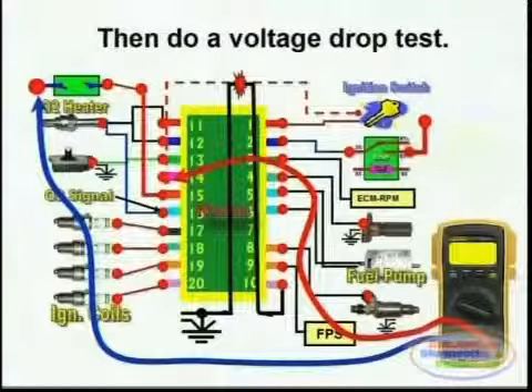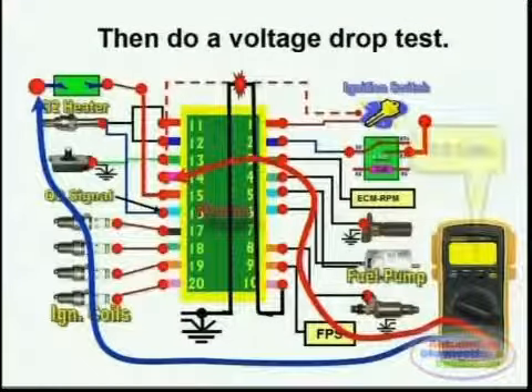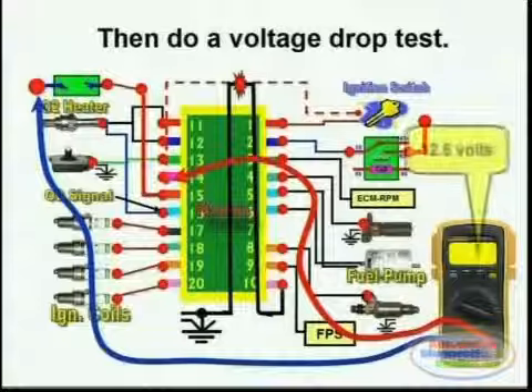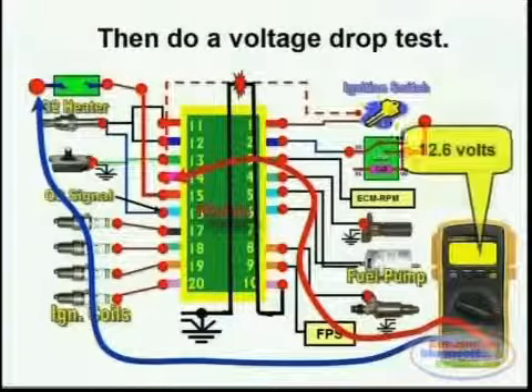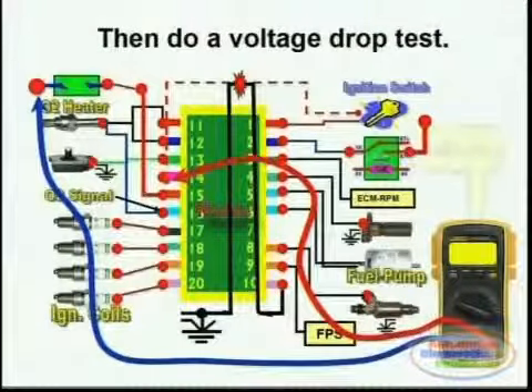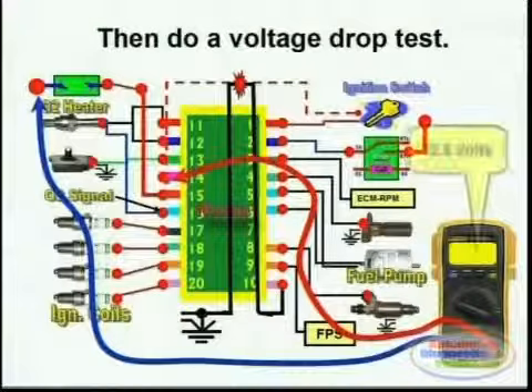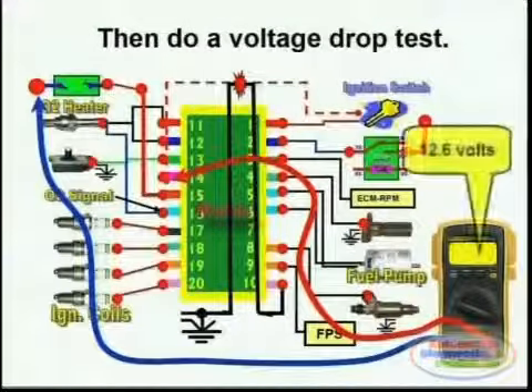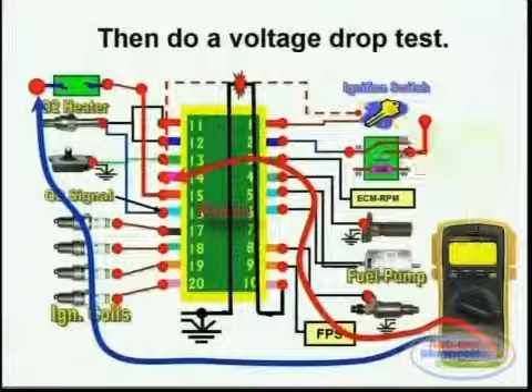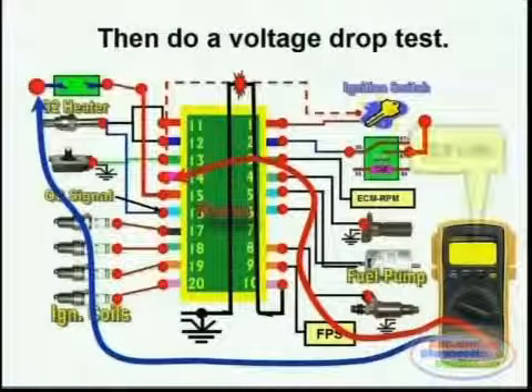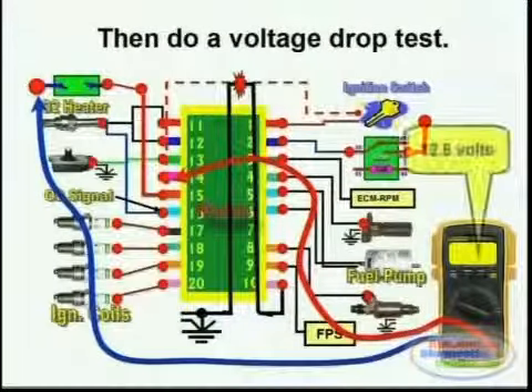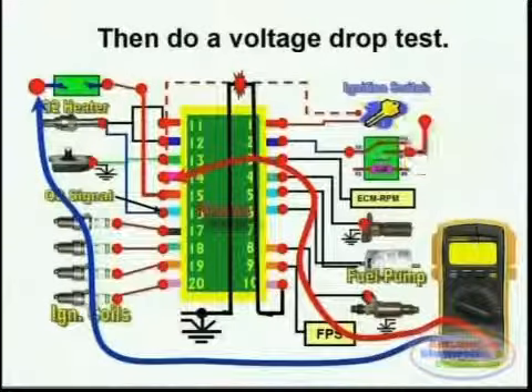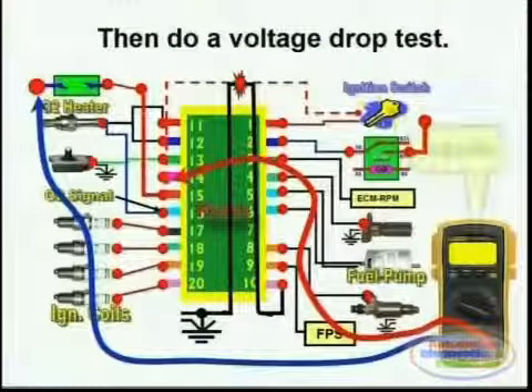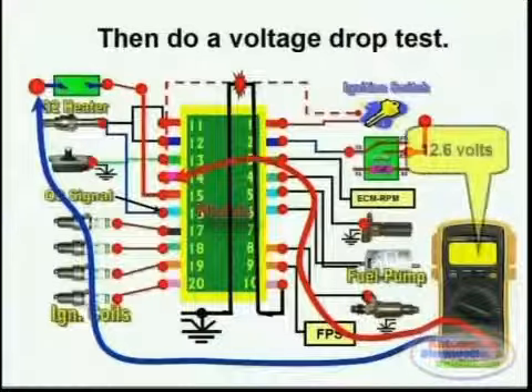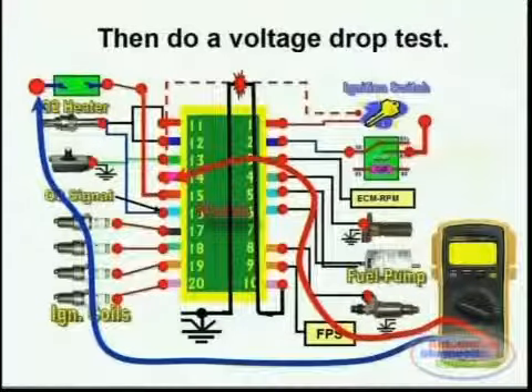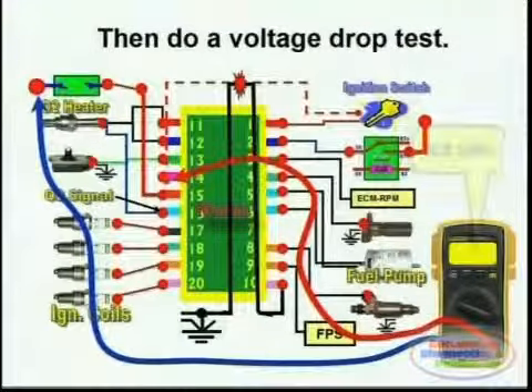Again, by doing a voltage drop between pin number 14 and the voltage source, you will immediately see that you have 12.6 volts across pin number 14 and voltage supply. It's not a good sign, and it indicates a problem - it indicates an open circuit. Even though you have a short, remember that the fuse that has popped is going to create an open circuit between the voltage supply and the voltage supply input at pin number 14 of the ECM.